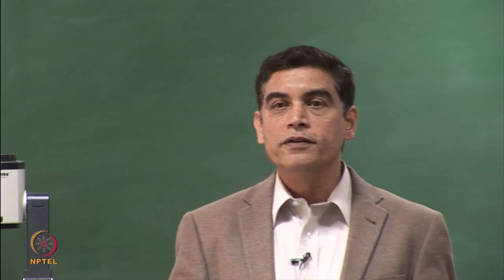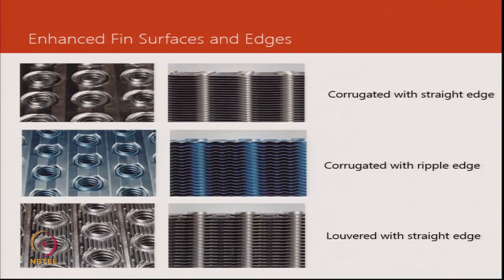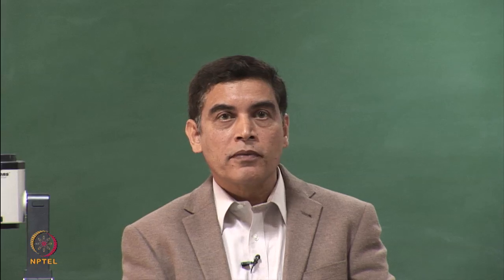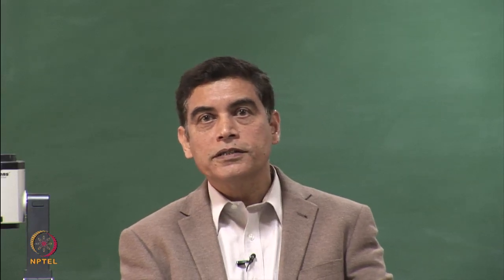So to enhance it, the first step is corrugating the fin. Instead of having a plain fin, the first one that we see on top is a corrugated fin, and then you could have variations in the edge of the fin. So you could have a straight fin, or you could have a ripple edge, and all these are means of increasing the turbulence and getting a better heat transfer. And finally, we cut the fin. Before it is assembled, we make louvers in it, so that further turbulence is generated in the path of air. And all of these types can be used in evaporators as well as condensers.